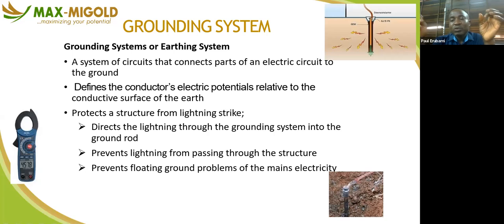So it's not only to protect human beings or facilities, it also helps to reduce the monthly bill. Because if the circulating current, that leakage current, is not conducted away, it will be circulating within your system, and it will show on your bill. You say, oh, why am I paying such an amount of bill? Whereas you failed to treat your earthing arrangement. So these are the things you need to pay attention to. Building electrical maintenance is very easy. It helps you to save cost, reduce risk, and maximize your profit.